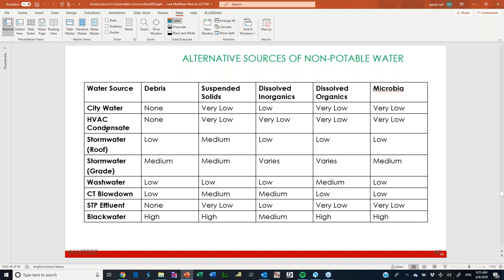For example, HVAC condensate has no debris, very low suspended solids, and very low inorganics, organics, and microbial content, particularly if the cooling coil is irradiated with UVC, in which case there will be virtually no microbia at all. This is essentially distilled water.